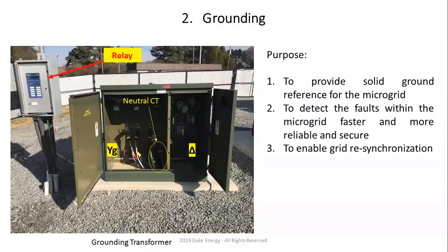Because if you have Y grounded floating Y transformers, essentially what happens is that there is no grounding reference in the 12.47 kV, so your relay at the PCC can see the grid side reliably, but it does not see the microgrid side at all, and you will see a lot of fluctuations. So that's the critical thing. A grounding transformer must be installed within the microgrid when you have distributed energy resources with a Y grounded floating Y. So if you had a generator, you don't need it, right?